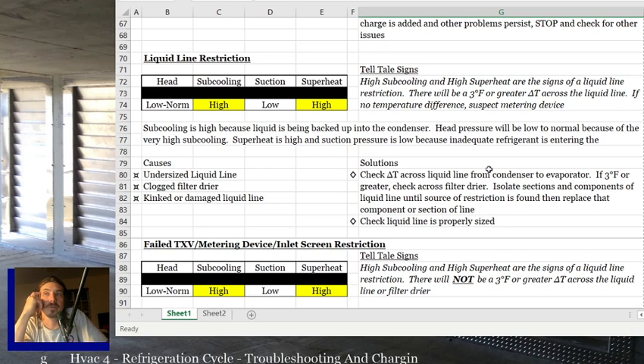For a liquid line restriction, the real sign is a 3 degree or greater temp difference across the liquid line. So if you measure the liquid line temperature at the exit of your condenser and then at the inlet of your metering device, basically, go from your condenser all the way to your metering device. If you have a 3 degree difference in the temperature in that liquid line, then you have a restriction in it. If there's no temperature difference, then the problem's probably at your metering device.